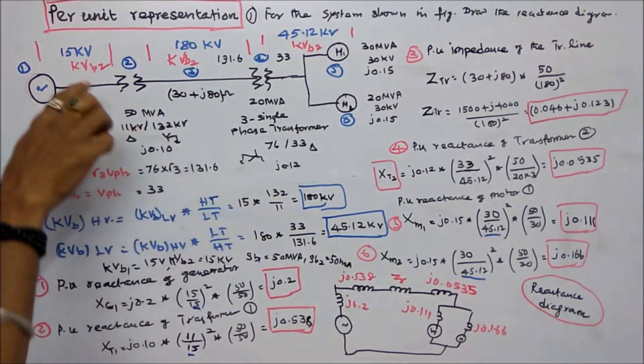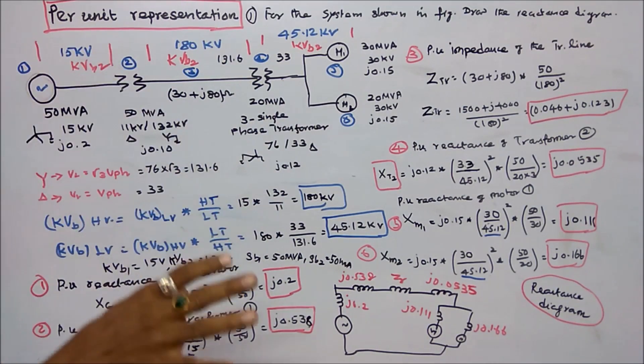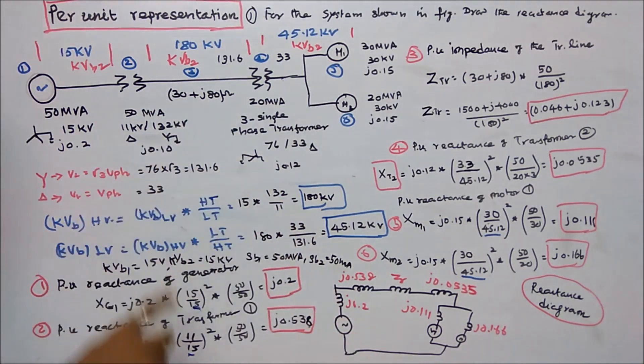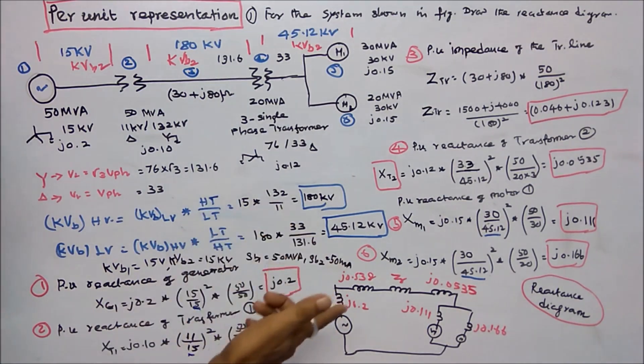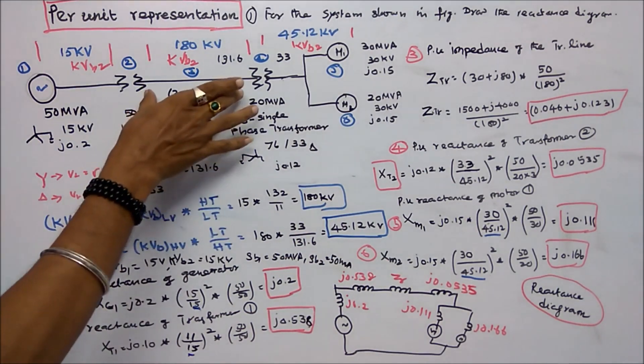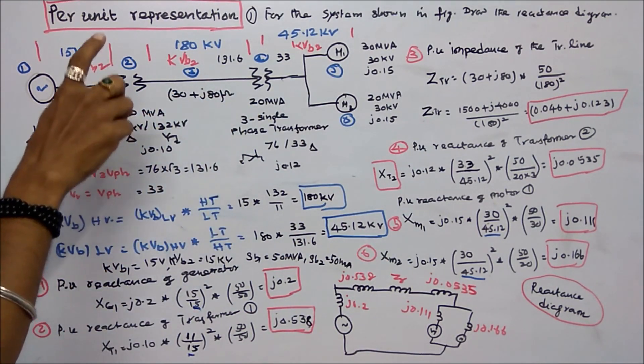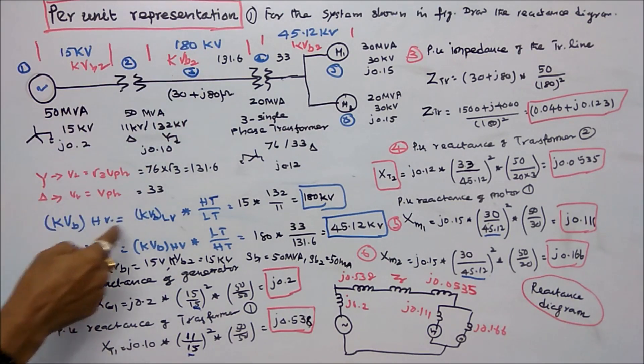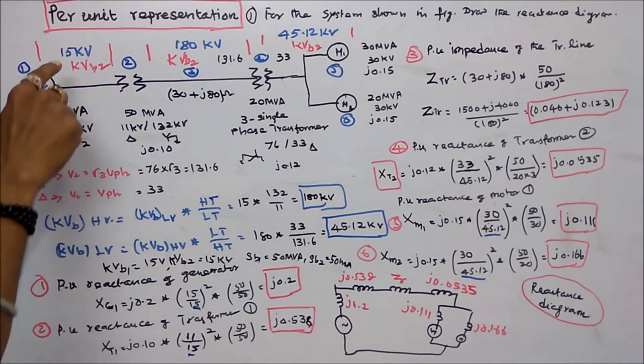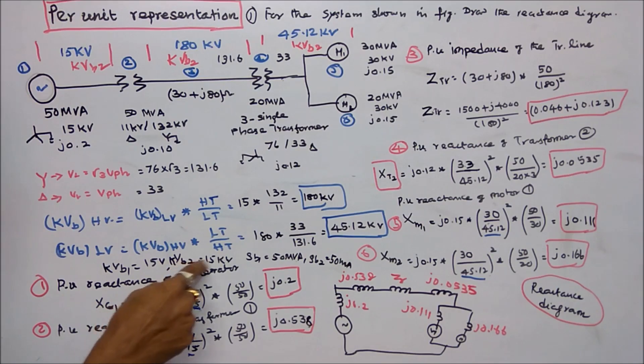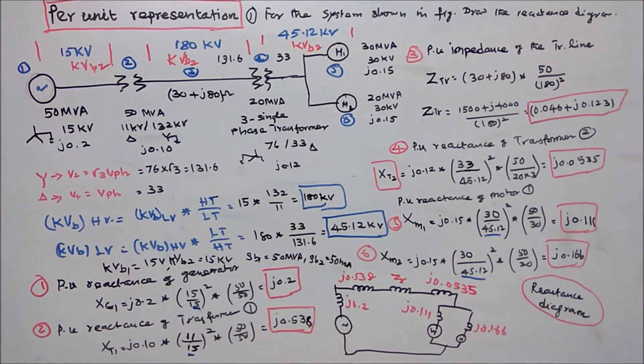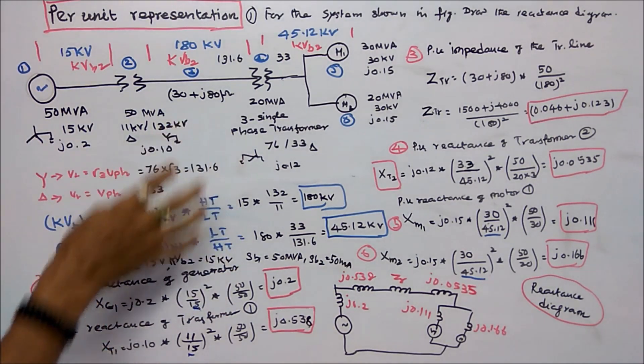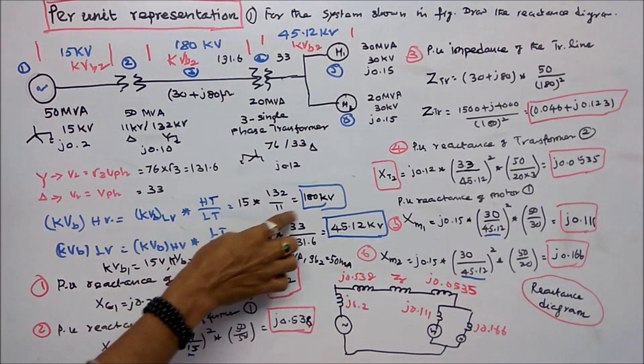We have to choose different kV bases. KVB1 represents old/given values and KVB2 represents new/chosen values. Similarly SB1 is given, SB2 is chosen. Chosen KVB2 is 15 kV and SB2 is 50 MVA. High voltage kV base equals low voltage kV base 15, times HT rating 132 divided by LT rating 11, giving 15 into 132/11, which equals 180 kV.